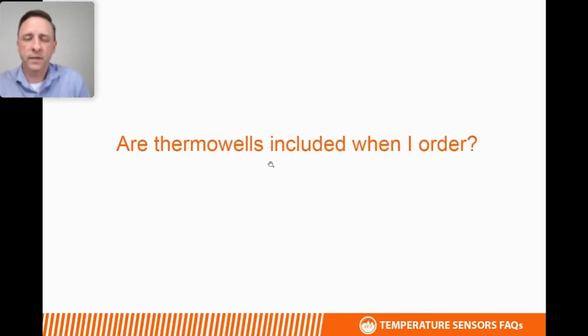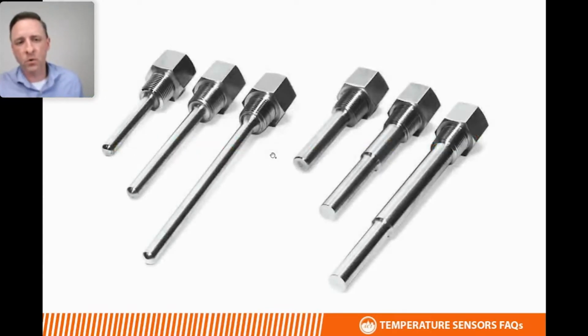Are thermal wells included with the immersion sensors when you place an order? Yes, our default part numbers include what we call a fabricated or welded thermal well. Those are the ones you see on the left-hand side of the screen, and that is included in our default part numbers. The immersion sensors can be ordered without a well, or they can be ordered with a machined well, which you see over on the right-hand side of the screen.